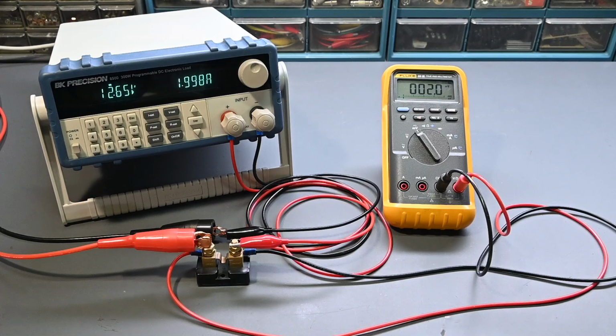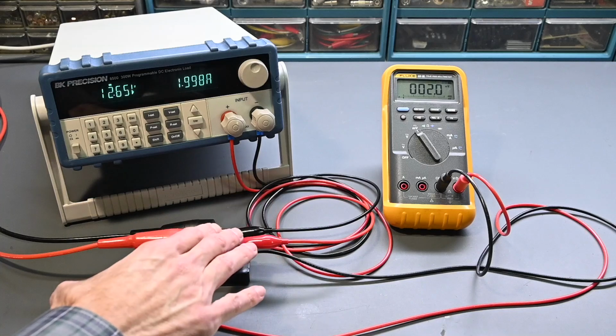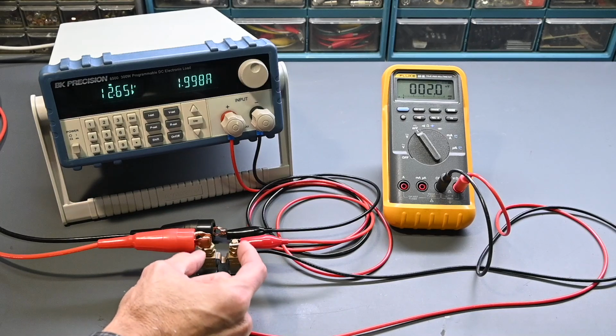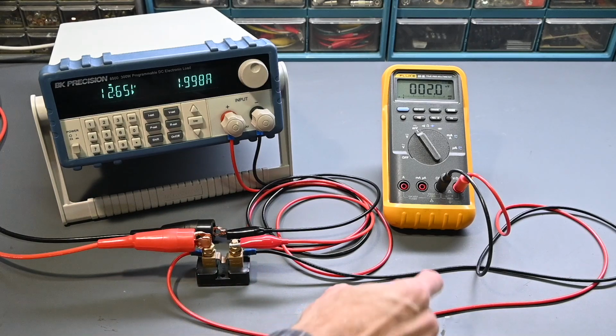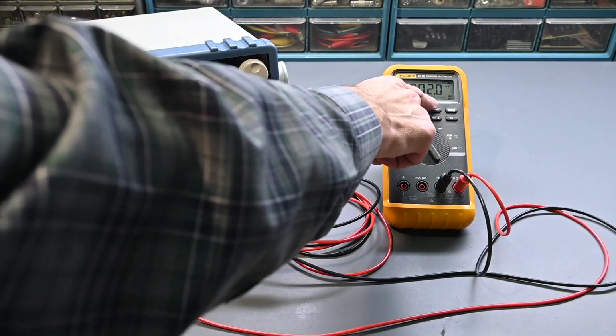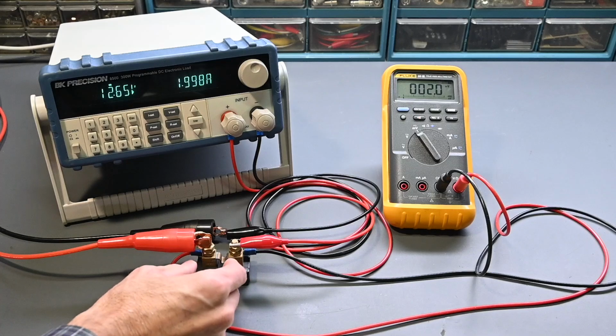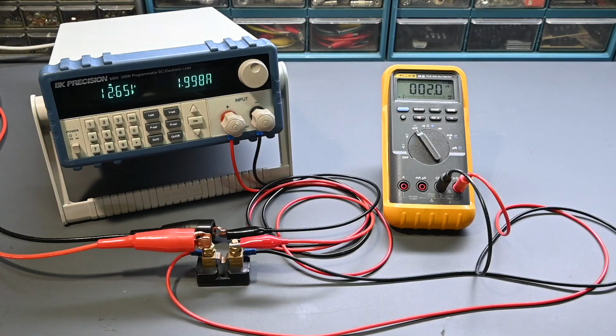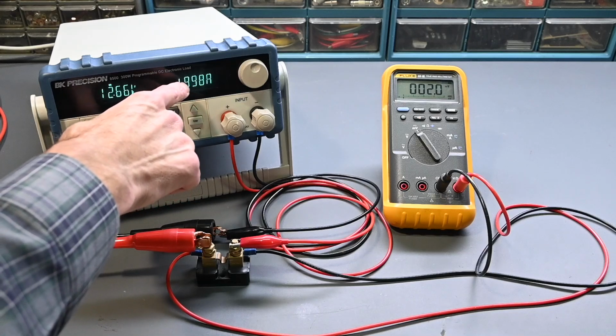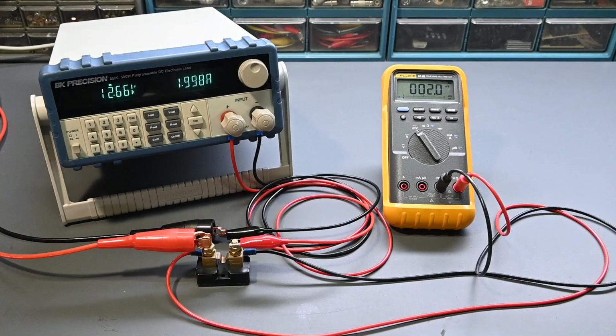So basically the same setup as we were using with the digital multimeter. We're measuring current, except now the shunt is measuring the current, and a voltage is being created across this shunt resistance that's on these two leads right here. They're going into the meter, and you can see it's measuring 2 millivolts. Now this particular shunt is rated up to 100 amps, and it creates 1 millivolt per amp. So you can see I have this set to 2 amps, so 1.998, so right at 2 amps, and 2 millivolts. Makes sense because 1 millivolt per amp. So you just have to do the conversion, and you can basically read the current directly right off the display.